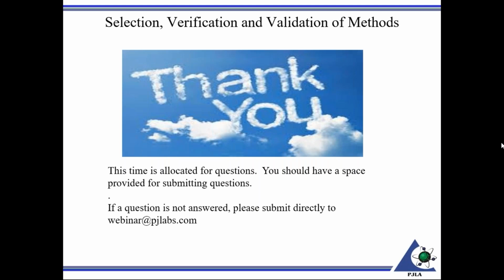How long do calibration and maintenance records need to be kept? I would say there is no requirement specifying that in 17025. In records, you have to establish retention time. As far as Perry Johnson Laboratory Accreditation is concerned, our reaccreditation cycle is every 2 years. So for those of you that are accredited with us, you need to at least keep them 2 years, just for that. But there is nothing in the standard that says you shall maintain these records for X amount of years.